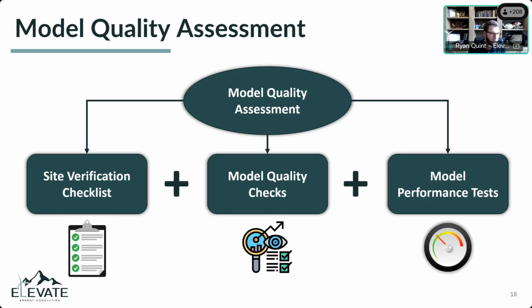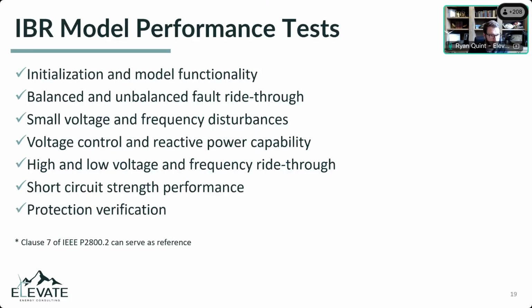Like I mentioned, the version controls, the model documentation, the flags, the protections - those types of things. And then does it pass the defined set of performance tests, if they exist, to know ahead of entering the queue whether my model meets the minimum level of performance? Then they're going to load it into the system impact study, and I may have grid interaction issues, but I need to know that I comply with a certain set of SCR requirements, etc.